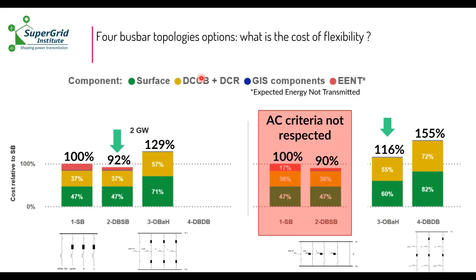So you need to compare only between the last 2, which are the most expensive ones, but the one breaker and a half ensures less cost of the protection system. I will come back to this later. This is the cost of the DCCB and the DC reactor in yellow. So with all this set, you chose the bus bar topology, but you still have not chosen the protection components. You need to choose what protection components you need at each departure.